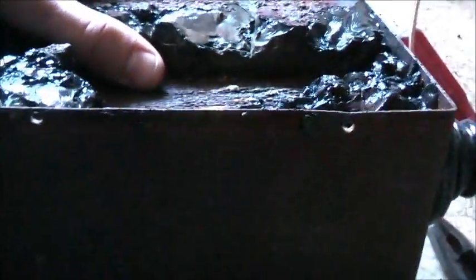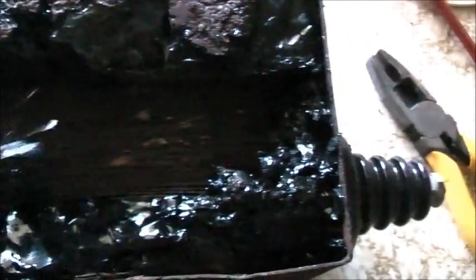You've got to dig out all the asphalt around it, see if that's still connected. But hopefully that's all it is. If I can fix that wire up, hopefully this may work again. Okay viewers, I got that little wooden spacer off, and the laminations are even rusty up here. Some moisture's been drawn up into the laminations, moisture's gone up and is going all through this.